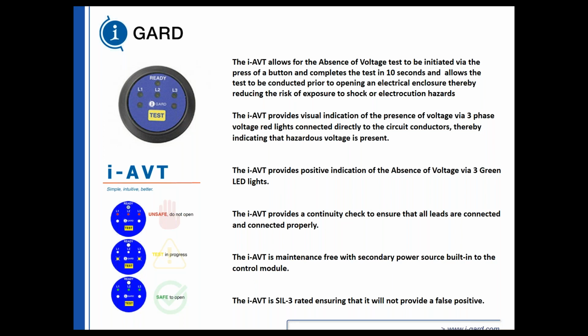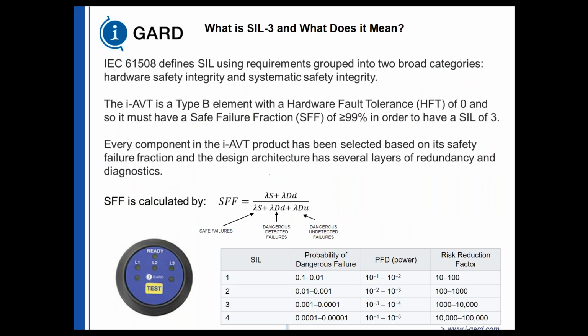It is maintenance free without a secondary power source, or the power source is built into the unit and is deemed maintenance free because it's a supercapacitor and has a lifespan far greater than that of a battery. The absence of voltage tester, the i-Gard i-AVT, is SIL3 rated, ensuring that it will not provide false positives. And we've spoken a lot about SIL3, so what does that mean exactly? And believe me, this is not an easy test to pass.